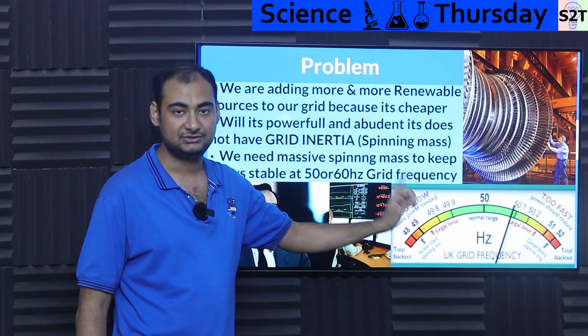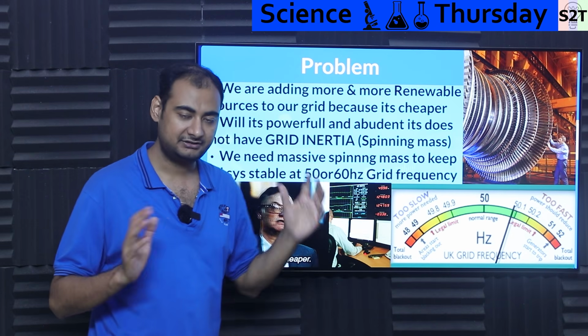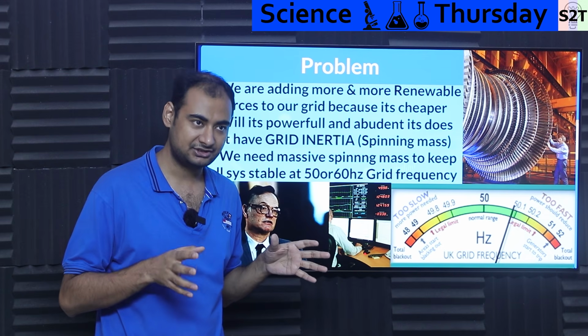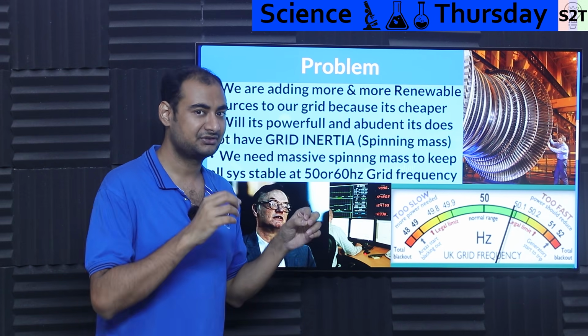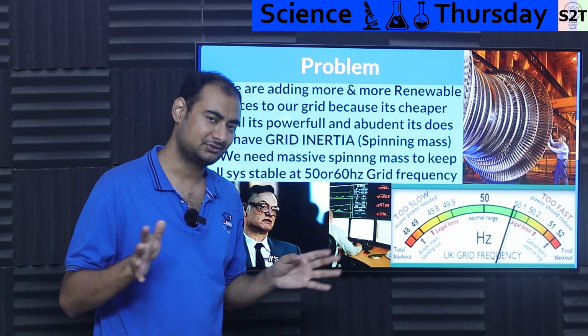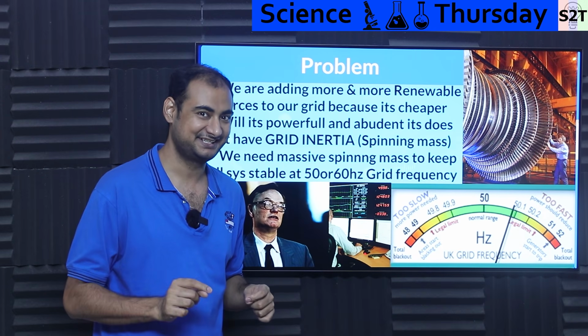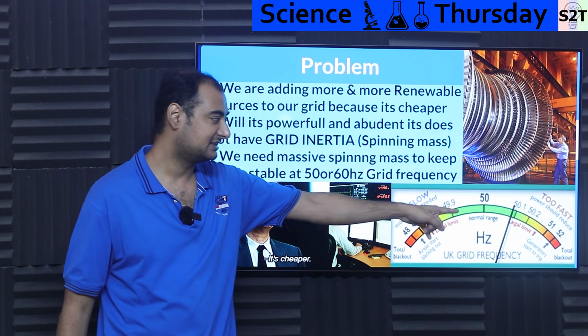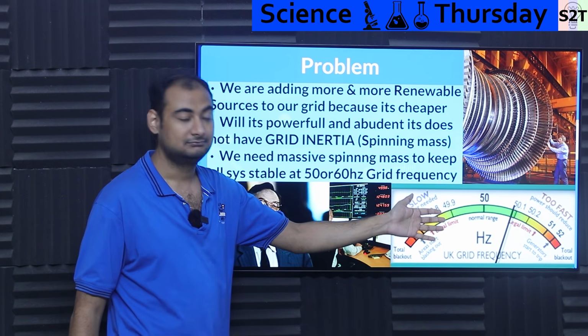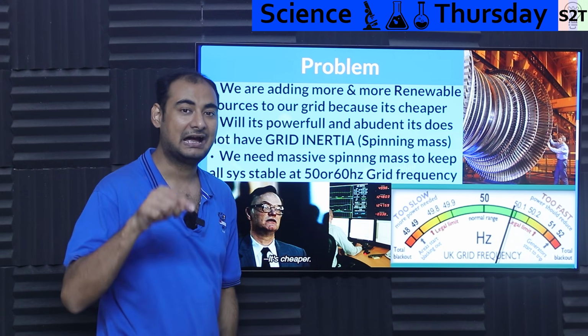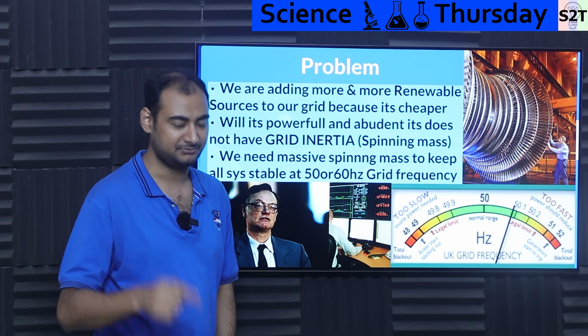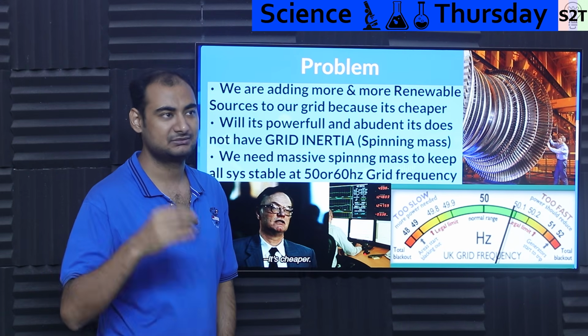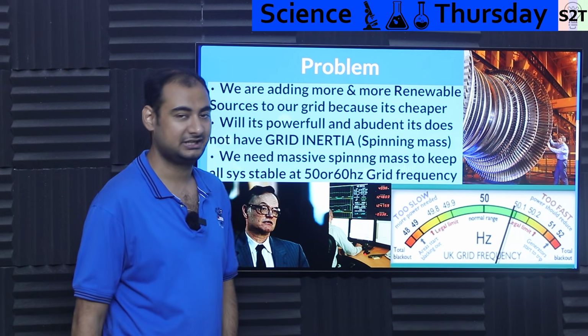At that point in time, you have to cut power. Every country has rules and regulations, and those regulations are not very tight in terms of voltage. They're like, yeah, low voltage, high voltage, you can handle it. They are very tight about frequency. So the moment it starts to cross, let's say, 50.5, you have crossed the legal limit, so you have to cut the power, meaning substations, the SCADA system will be like kaput. It will start shedding load.